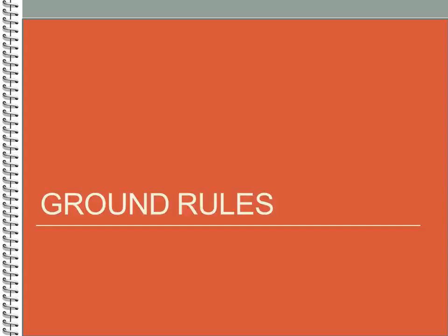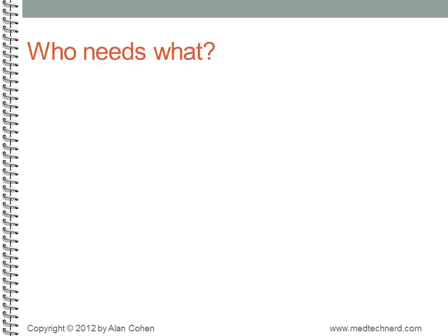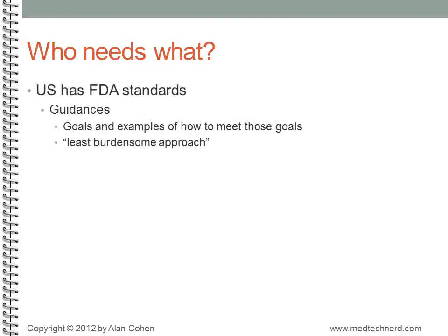Before we dig into the standards themselves, let's get a little context by reviewing the ground rules of selecting and using standards. We generally adhere to standards because we have to in order to comply with government regulations. In the U.S., the Food and Drug Administration creates the regulations that apply to medical devices. For most device developers, the FDA documents that are of the greatest importance to them are the FDA guidances.